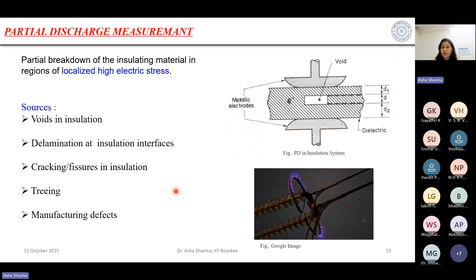So when we say partial discharge measurement, how can I detect the partial discharge? Let's say this is my solid insulating material, and the partial discharge is within the material. I am not able to see it, right? But how can I measure it? It can be measured like this. Let's say this is my whole insulating material, and some void or defect is present here. Again, the dielectric or insulating material is completely a capacitance, if I am not considering the resistance effect.